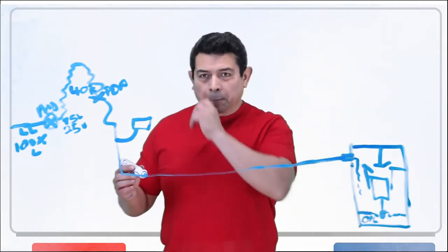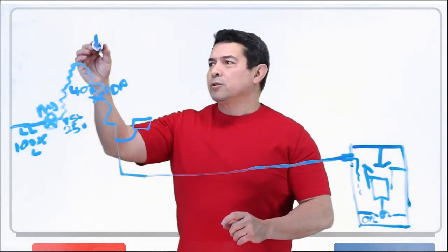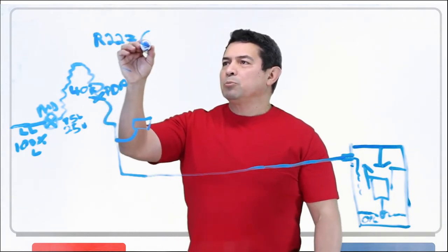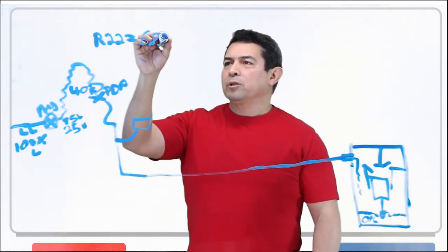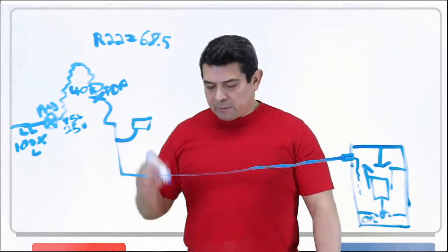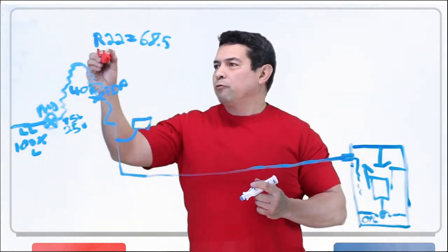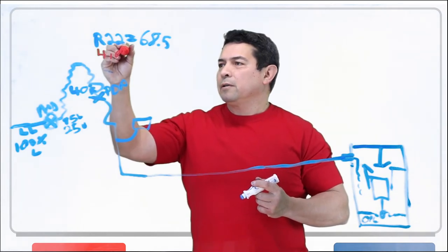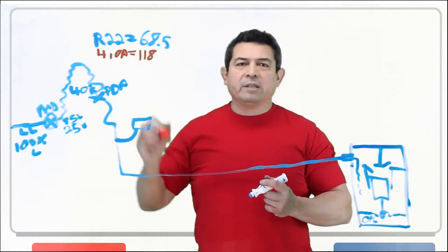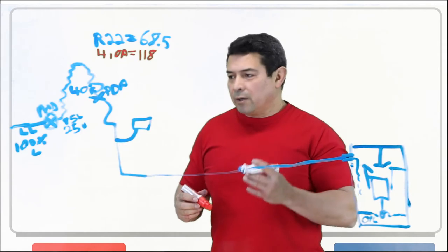But let's take a look at this right here. If this is 40 degrees, we know that if we're using, let's say, R22, then the pressure should be 68.5, 68 PSIG right there. If this happens to be, let's say, 410A, then this is going to be 118 PSIG. So the pressures are different, but the temperature is going to stay the same.